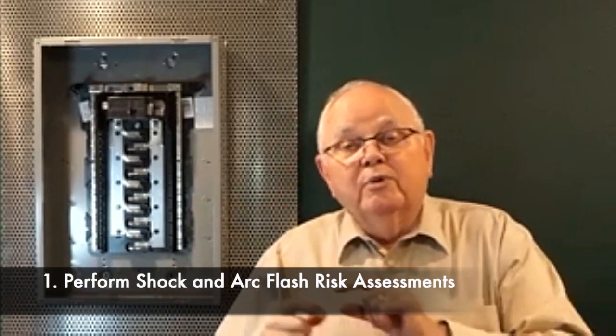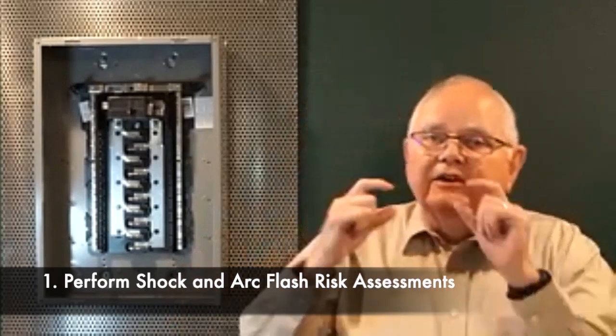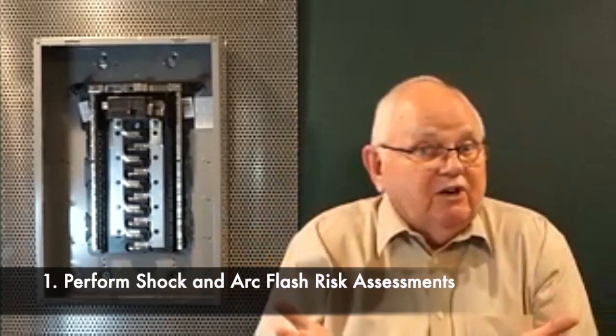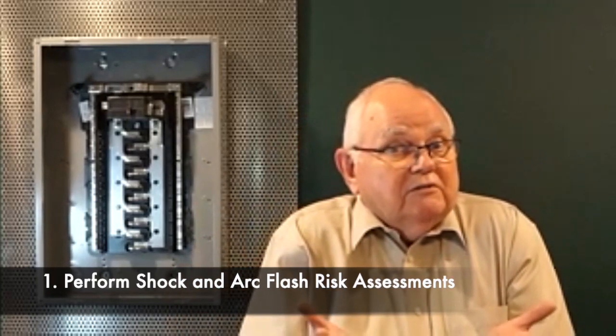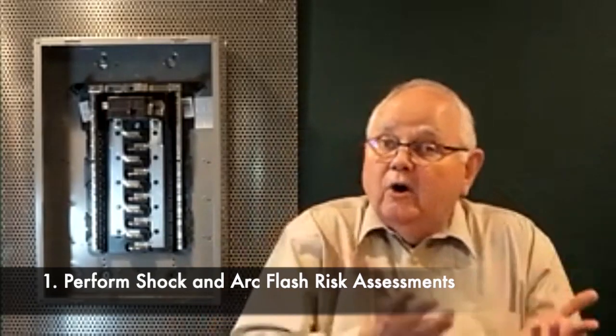So the first thing we always have to do, there are 5 items we're going to go over today, 5 major areas, I should say, if we're going to go out and do this job out in the field. The first thing we have to do is we have to identify the hazards. We have to perform a risk assessment. There are 3 reasons that we do the risk assessment then. When it comes to electrical work, we have to do both a shock risk assessment and an arc flash risk assessment, because as I said earlier, that's the 2 ways we can get hurt, shocked or worse yet electrocuted, or we can be burned.